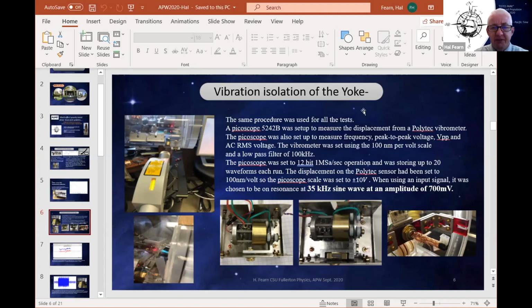Now, you can see this picture here. You can actually see the laser beam, the red laser beam hitting the Faraday cage. But then I'd also shine it on the arm, which is over here. You can see my cursor. It's over here to the left. And we found that virtually none of the vibration of the Faraday cage was getting to the beam arm. I mean, the frequency was completely different, and the amplitude was virtually nil. I really had to search around for anything at all that was an amplitude. It was almost like background noise.